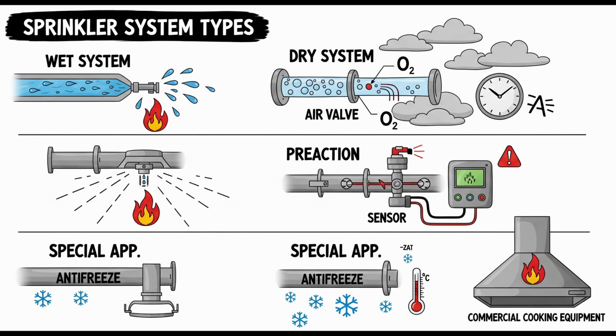Okay. What's next? Second is non-interlock. Here, water enters the piping upon operation of either the detection devices or automatic sprinklers activating. Either. So if a sprinkler head pops before the detector senses anything, the valve still opens. Yes. Or if the detector goes off first, the valve opens. Either event triggers the valve. It provides a sort of backup if the detection fails, or is bypassed by a very rapidly growing fire that opens a sprinkler first, the system still activates. Interesting. More redundancy there. And the third type?